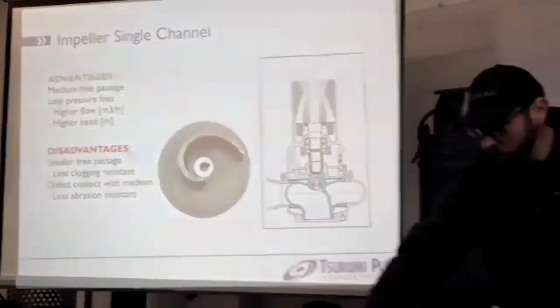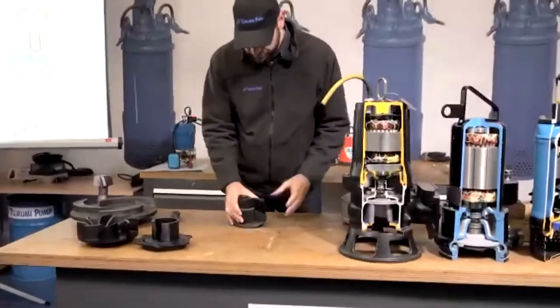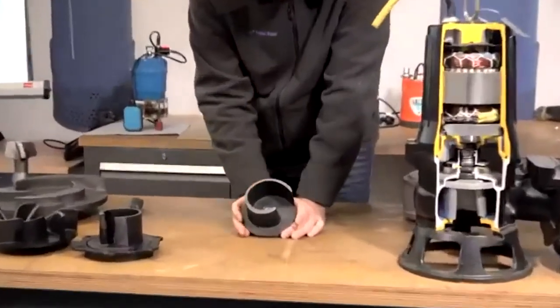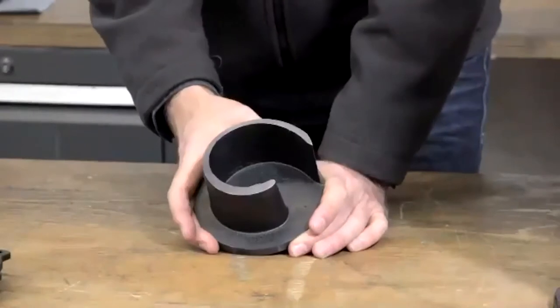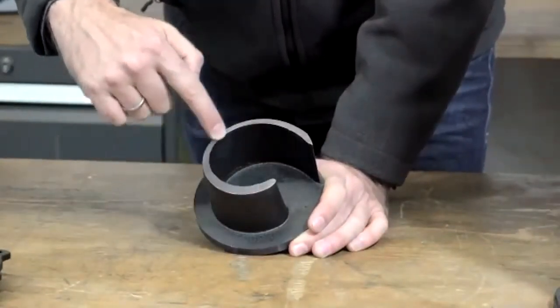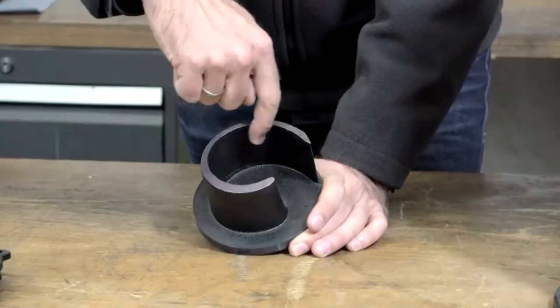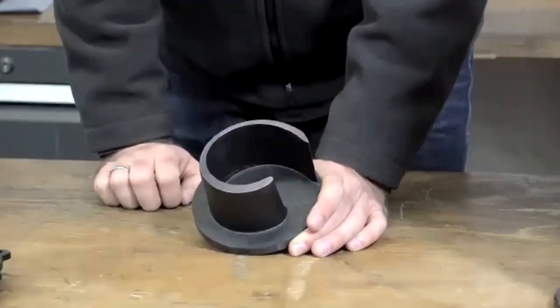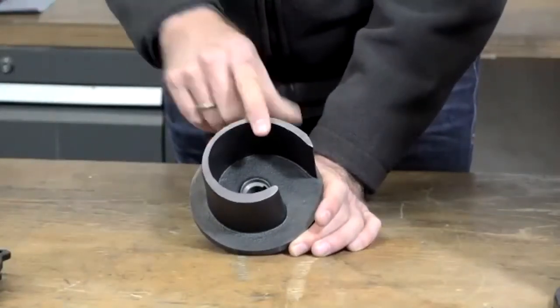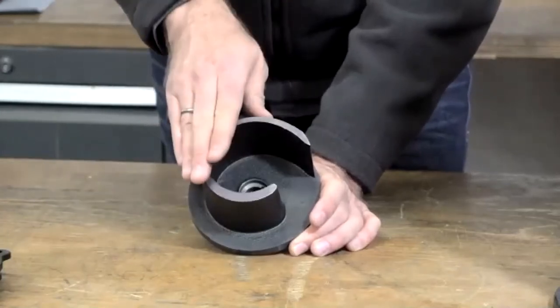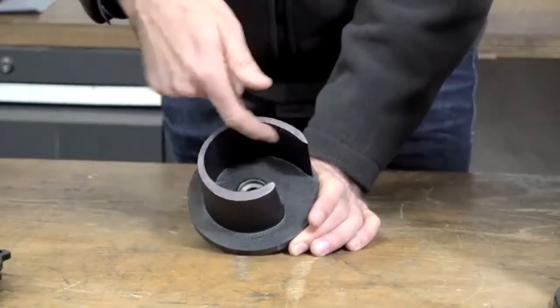Looking at a single channel impeller example: its basic structure is round like every impeller, but it has a single vane going all around. The medium enters the impeller, is accelerated in direct contact with the impeller vane, and is discharged. You can also see why we have less abrasion resistance — the wide area within this impeller is in direct contact with the medium, and abrasive substances will wear away at those direct contact positions.